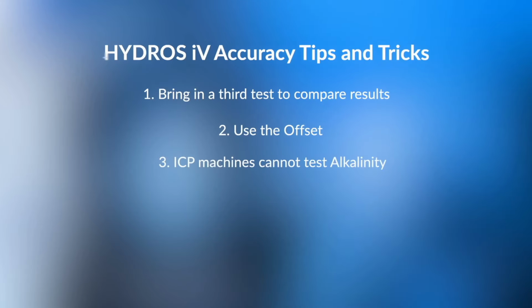I've gotten this on support. Well, my ICP said that my alkalinity was 7. Well, here's the thing: ICP machines cannot test alkalinity. They can't. If an ICP test tells you that they're testing alkalinity, somebody is drawing water and running a titration test for you, because ICP machines can only test individual elements, and alkalinity is a combination of things. It's not just an individual element. And also, how long was the water sample in the vial before they actually got to test? Because the bacteria left in the vial will also, yes, as the bacteria decays or consumes, the alkalinity in the water will change.